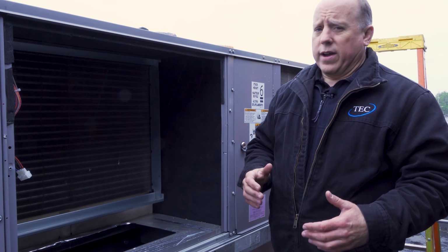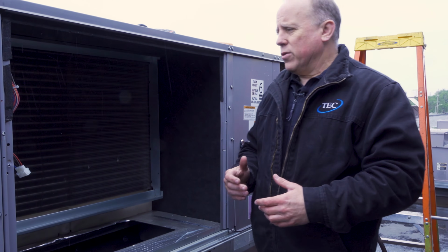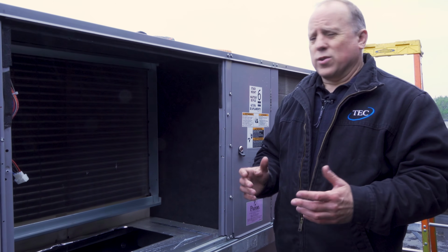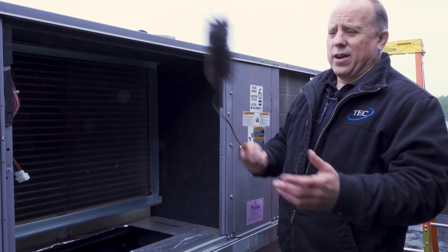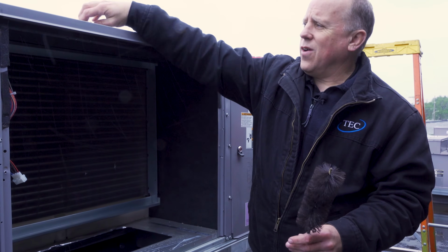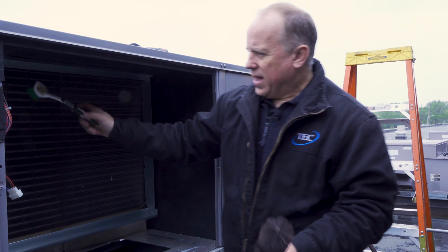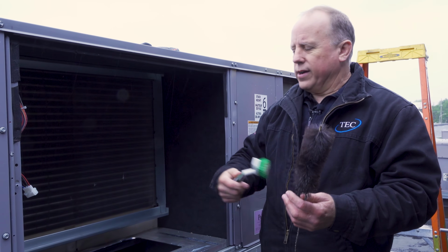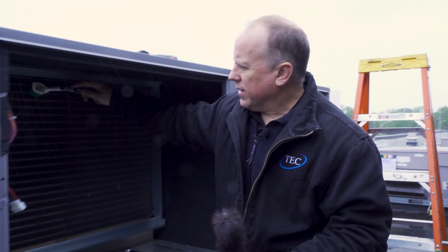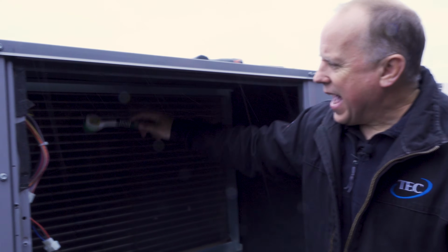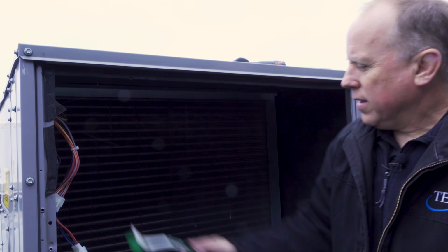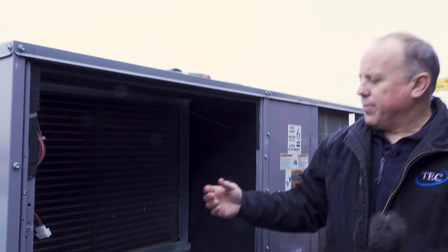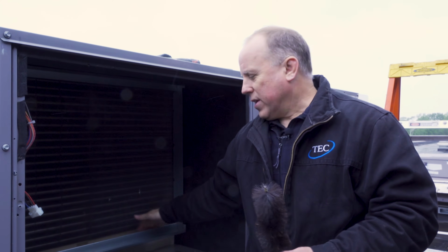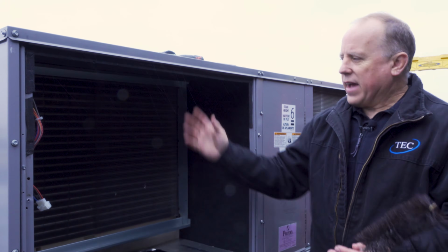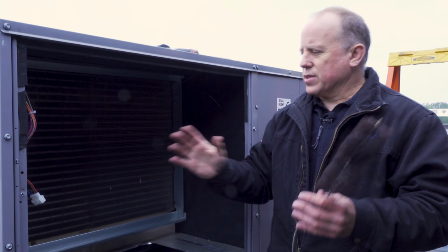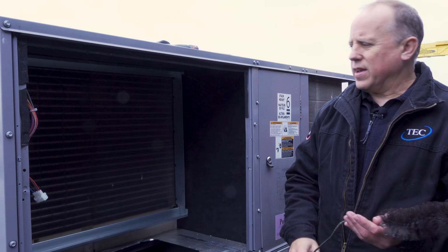If you get to a coil that's really dirty, really bad, you come up on a unit that hasn't had filters in a while, you also have options of brushing a coil off. Here's a simple furnace brush, any type of brush. You could take it carefully, again, because we don't want to push stuff into the coil. We don't want to damage the coil. Just lightly brush down and knock any of that debris off the coil. And then we could take a vacuum and clean that up, or as we get it down in the drain pan, we could just scoop it out and throw it out. But a vacuum sometimes will suck some of that debris off. It just kind of depends whether that's wet or not at the time you're dealing with it.